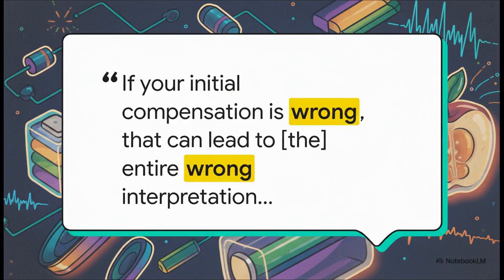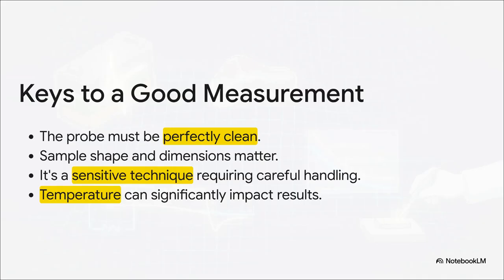And I can't stress this enough. That first step, calibration, is absolutely critical. As this quote from our source material makes very clear, if your initial compensation is off, you can end up with a completely wrong interpretation of your data. It is the foundation that the entire experiment is built on. Precision is everything in this game. The probe you use has to be perfectly clean, because even a tiny bit of residue can throw off the readings. The sample's shape and its size matter too. And you have to watch out for things like temperature, which can have a huge impact. It all goes to show that EIS is an incredibly powerful, but also very sensitive technique.